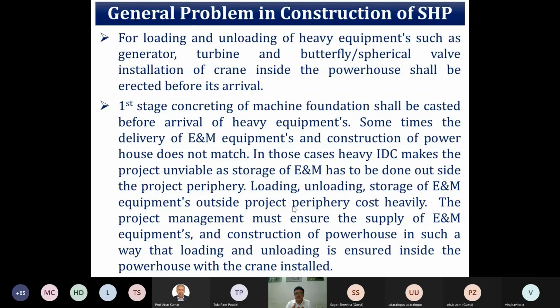So this should be planned such that machinery from the E&M equipment supplier goes directly to the project site. Project management must ensure that supply of E&M equipment and construction of the powerhouse are coordinated so that unloading happens directly inside the powerhouse using an installed crane. Since the generator and turbine are very heavy equipment - for example, a 7.5 megawatt generator may weigh around 40 tons - you cannot expect a crane to be available in these remote areas to unload such heavy equipment. So the crane installed inside the powerhouse should have the capacity to unload these heavy materials, and this should be planned properly.